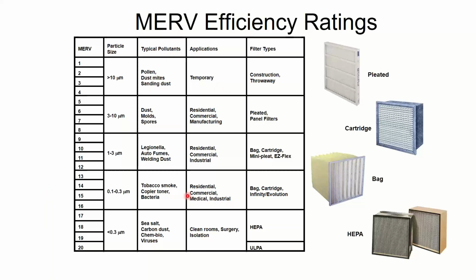So the MERV rating is going to tell us how well a specific filter that's tested can catch certain size particles. Here are my particle sizes down this column. I have everything from really tiny stuff to 1 micron, 3 microns, and stuff bigger than 10 microns, and what MERV rating they'd get. If you're only able to catch 10 micron particles, you basically have no MERV rating. You're MERV 2, 3, 4, which is absolutely useless. The crappiest filter you could probably even get is a MERV 6. I guess you could probably find one that's crappier, but the crappiest one you would ever want to put in a building historically, prior to COVID, would be a MERV 6.